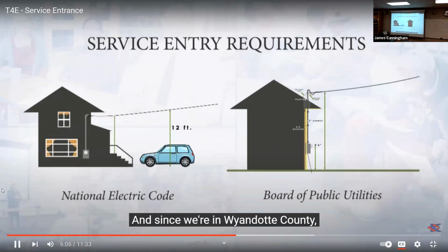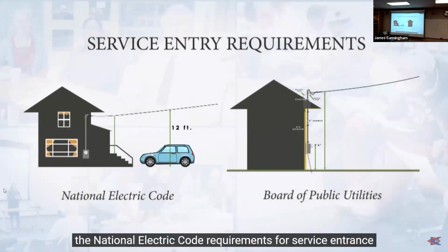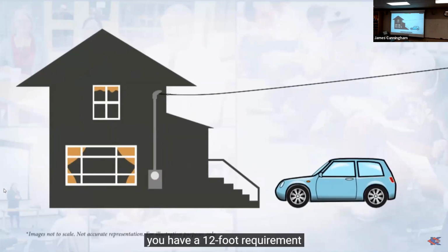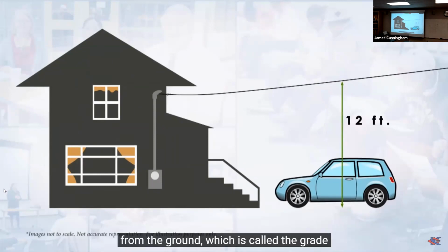County, the National Electric Code requirements for service entrance will be superseded by the Board of Public Utilities requirement. Over here on the National Electric Code, you have a 12-foot requirement from the ground, which is called the grade, up to the service entrance drop, which is the actual conductors coming from the utility, that has to be at that height in order for it to be the proper clearance.